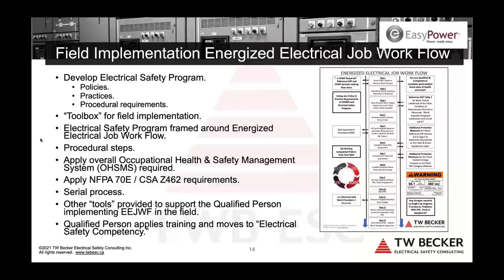So develop the program. It's a toolbox for field implementation framed around the energized electrical job workflow, the procedural steps in this workflow. Apply this workflow against your occupational health and safety management system requirements. A field level hazard assessment is required first to identify all hazards. For larger industrials, they may have a separate safe work permit, separate from what we would call the energized electrical work permit in 70E or Z462. But this needs to be customized around how ultimately jobs are given, I'll say it, work order execution, right, by the maintenance qualified person.